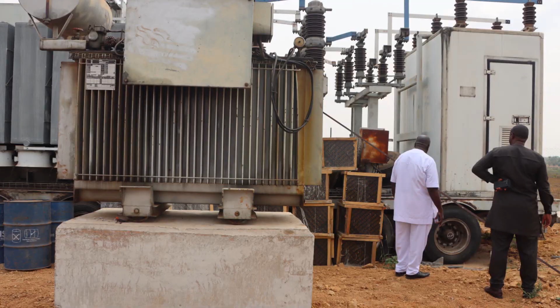The 40 MVA transformer will radiate 3 units of 33 kV feeders to serve the airport. Install it so that we can radiate at least 3 feeders - 2 33 kV feeders plus 1 spare. Those 2 feeders will be dedicated to the airport, and the environs too will be served, maybe with the spare. But once this is developed on 330, we will remove this mobile transformer - it's a stopgap measure to serve the airport now.